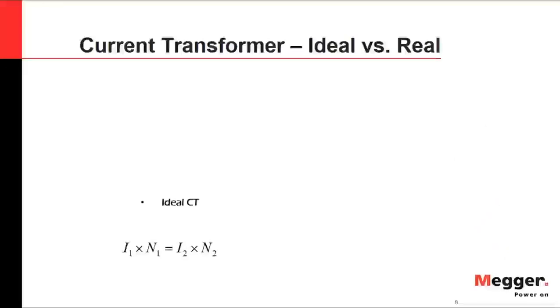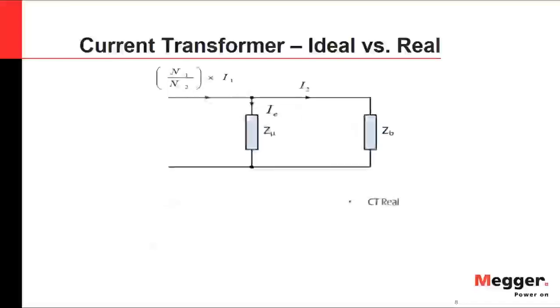In the ideal condition of a CT, the relation between the current flowing in the primary and the number of turns is equal to the current flowing in the secondary winding. However, a real current transformer is not ideal. The magnetizing circuit and magnetizing impedance will generate an excitation current that must be taken into account.